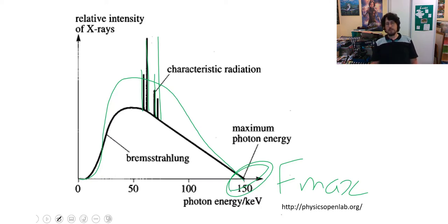So what we've now covered is increasing the voltage across the tube and increasing the current. Voltage increase results in a greater f max. A current increase results in a greater intensity. And a change in the metal target will change the location of the characteristic x-radiation peaks. Thank you.